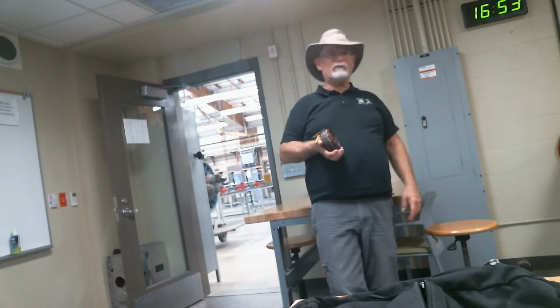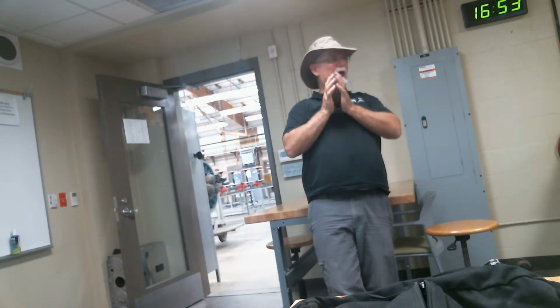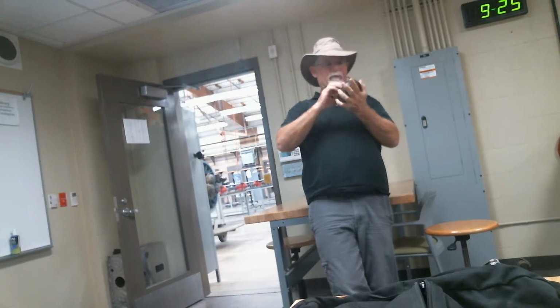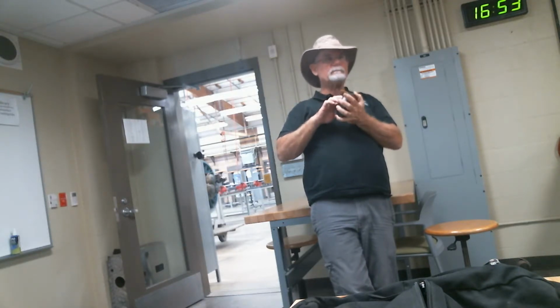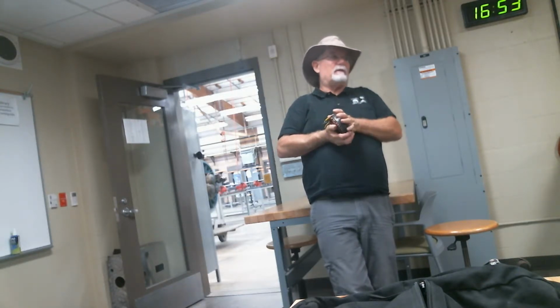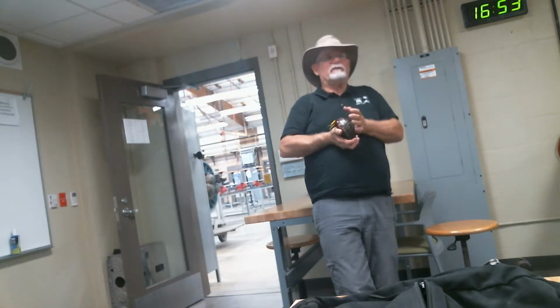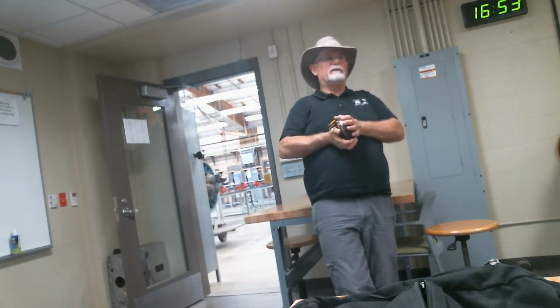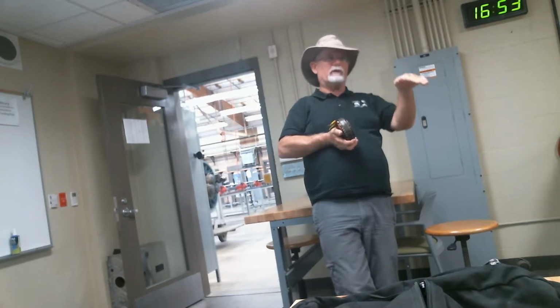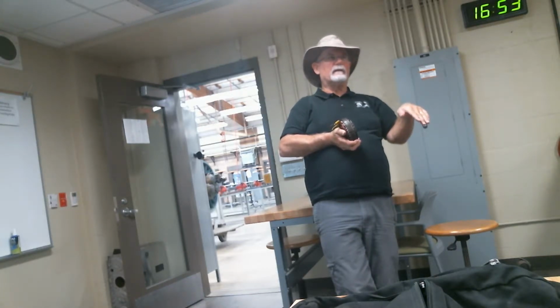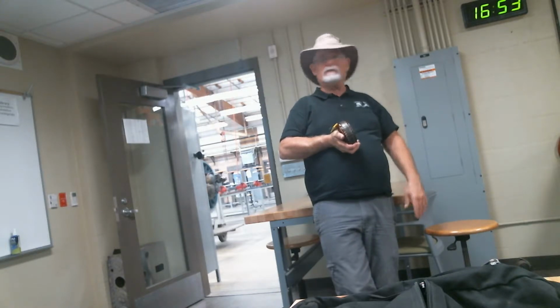So as this thing goes up in speed and load output, armature reaction gets worse. The more load you put on it, the more it distorts, and it just doesn't put out any more current. That's it, it's max. So if you put more load on it, the voltage is just going to start declining. More load, voltage declines even further.